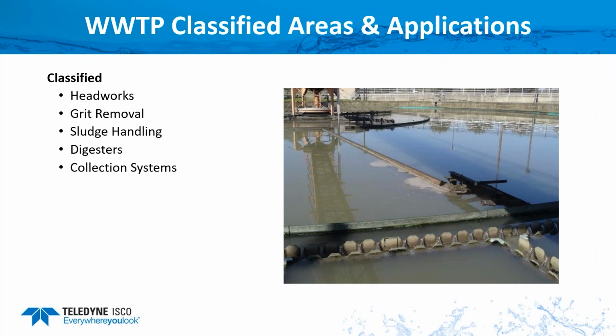Now, wastewater treatment plants have classified areas that I mentioned, and where you're going to find that is usually around the headworks, the grit removal, the sludge handling, digesters, and in the collection system. So pretty much everywhere up front where you could have gases build up that could potentially create a spark.